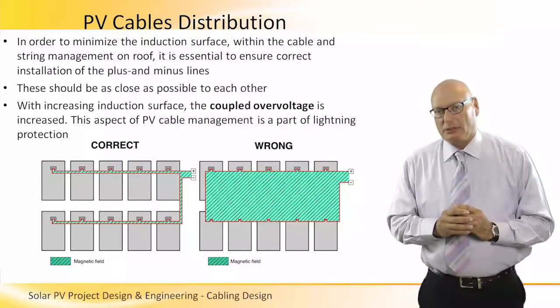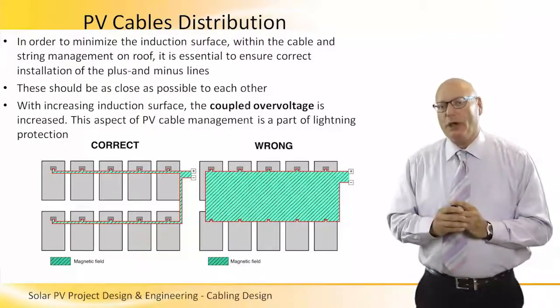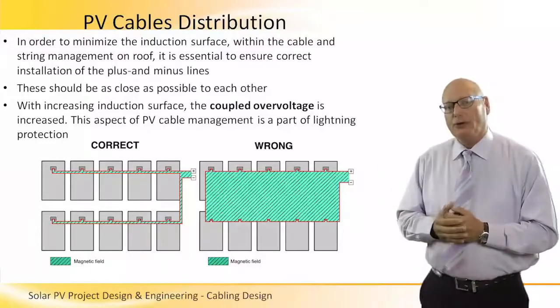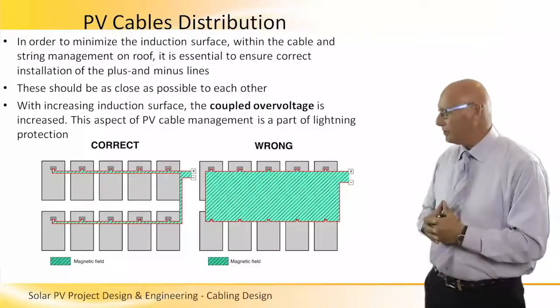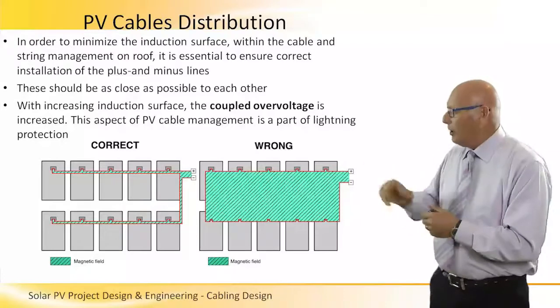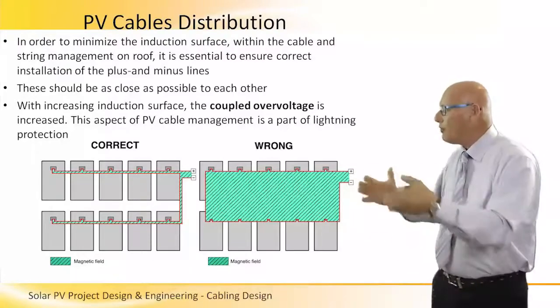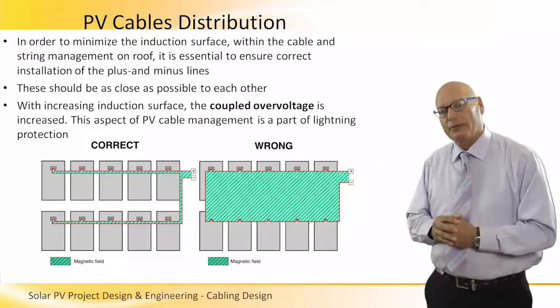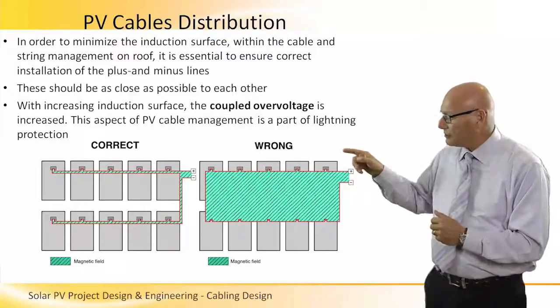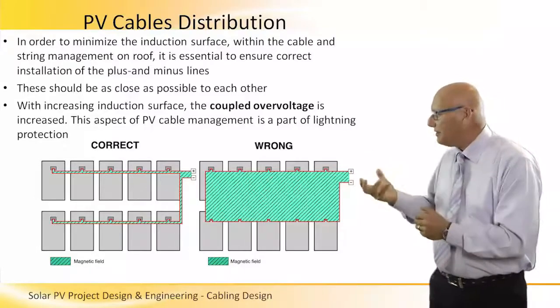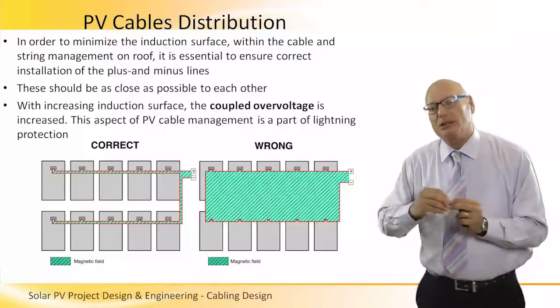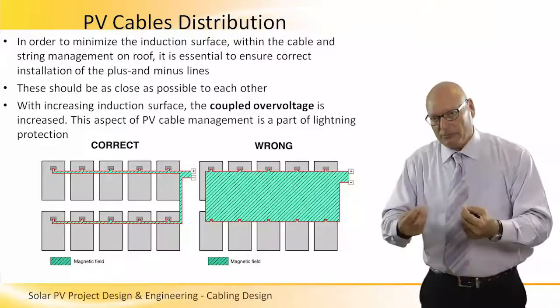Regarding cable distribution, there are two ways — correct and incorrect ways — of distributing the cables on the DC side. On the left-hand side we see the correct way of running cables under an array to connect all the panels together. We connect panels in one row in series, connect the second row in series, and then combine the two rows only very close to the junction box. The wrong way is taking the first row and continuing to the second row, increasing the magnetic field that these cables create. We want to minimize the magnetic field because we want to minimize the coupled overvoltage generated by it.